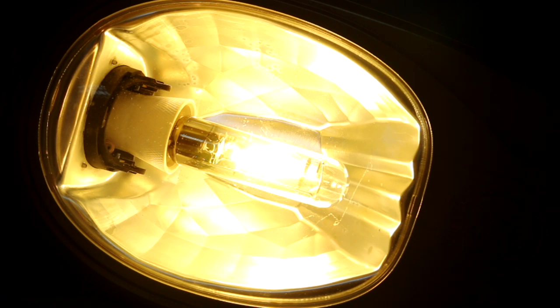And slightly dimmer, it's only 12500 lumens whereas the standard 150 watt SON is 17700. But that's at 20 percent color rendering. This has got a 65 percent color rendering index, which means it's quite good at displaying colors.